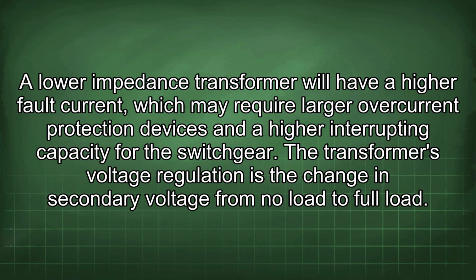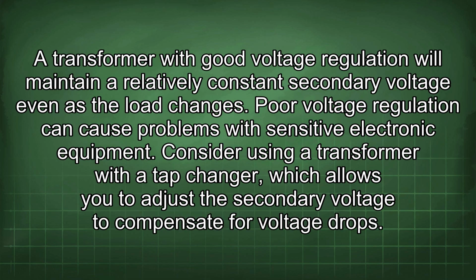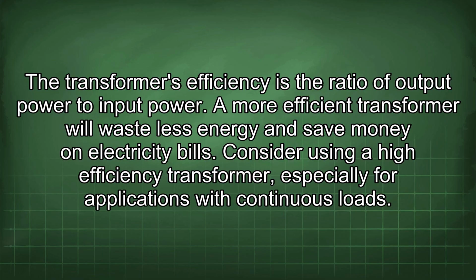The transformer's voltage regulation is the change in secondary voltage from no load to full load. A transformer with good voltage regulation will maintain a relatively constant secondary voltage even as the load changes. Poor voltage regulation can cause problems with sensitive electronic equipment. Consider using a transformer with a tap changer, which allows you to adjust the secondary voltage to compensate for voltage drops. The transformer's efficiency is the ratio of output power to input power.